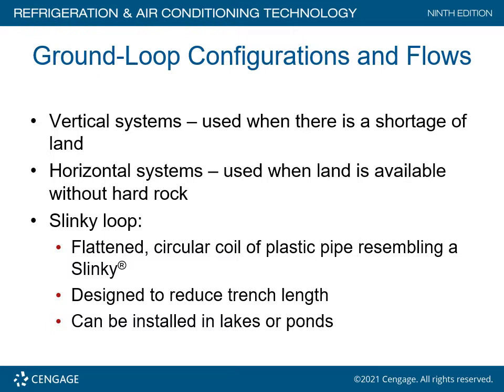Ground loop configurations: vertical systems are used when there is a shortage of land; horizontal systems are used when land is available without hard rock. A slinky loop is a flattened circular coil of plastic pipe resembling a slinky toy. It is designed to reduce trench length and can be installed in lakes and ponds.